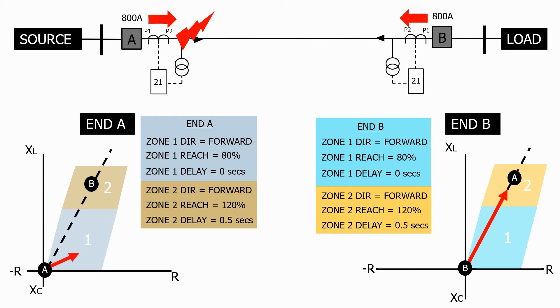The fault is now seen by the impedance relays at end A and end B. The end A impedance relay sees it in zone 1, whilst the end B relay sees it in zone 2. The zone 1 at end A is instantaneous and trips immediately, clearing the fault current from end A.